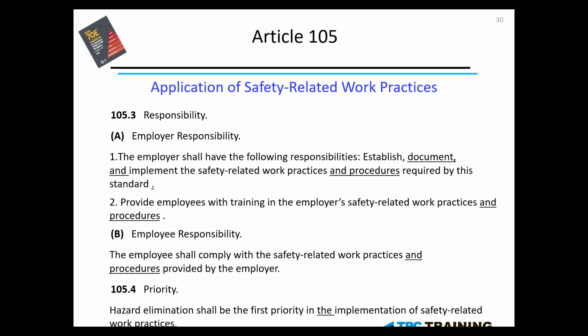And you see right there, 105.4, the priority in a very small sentence there is hazard elimination. It shall always be the first priority to implement a safety-related work practice. Whenever possible, we eliminate the hazard, de-energize. If it cannot be de-energized, then we must protect against it.